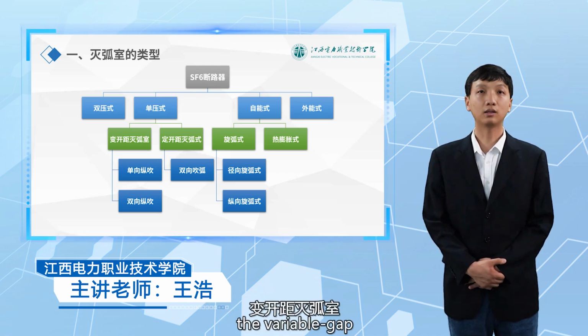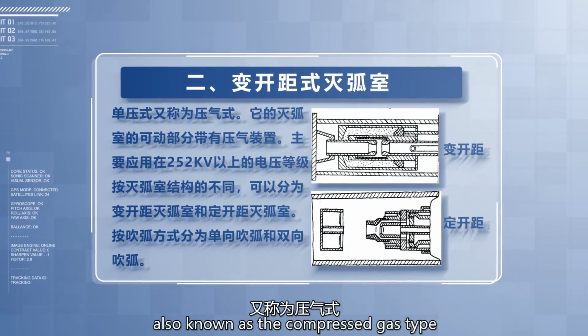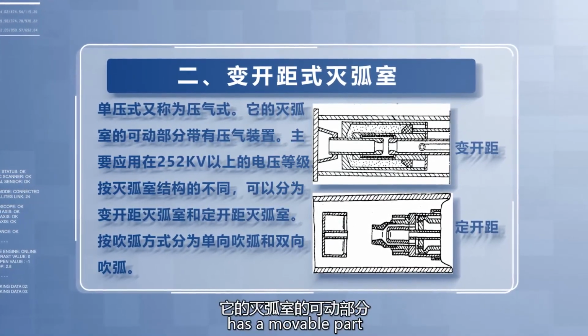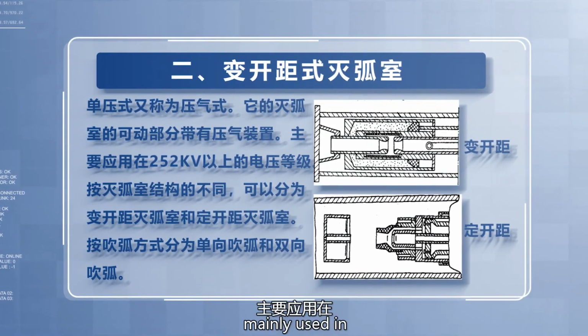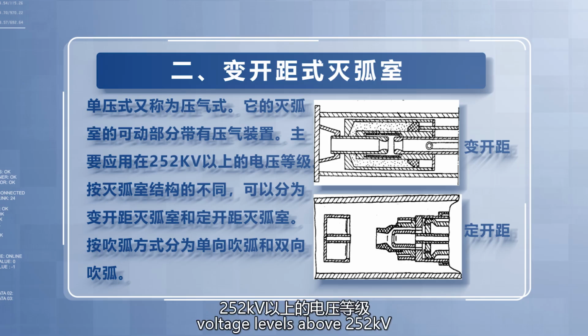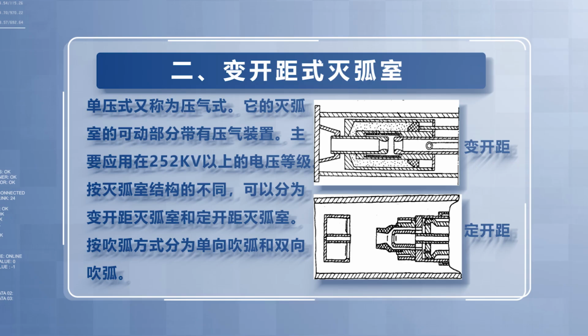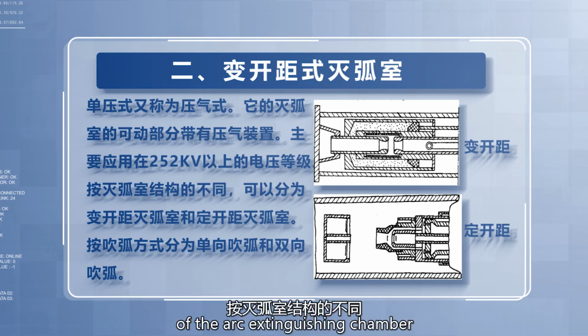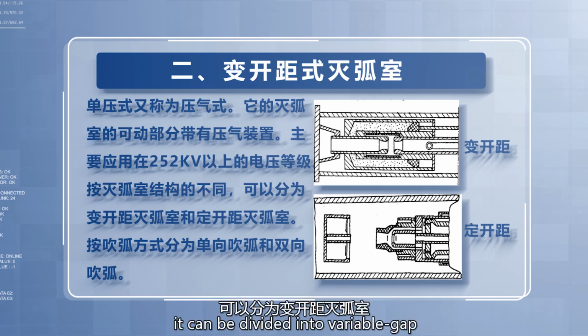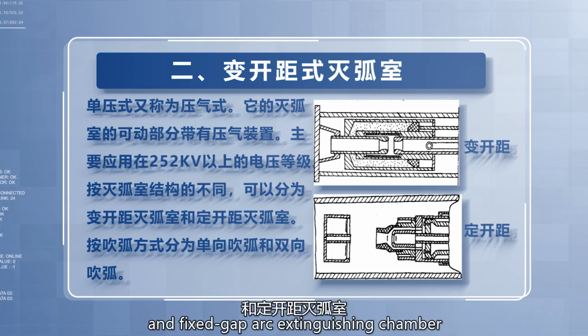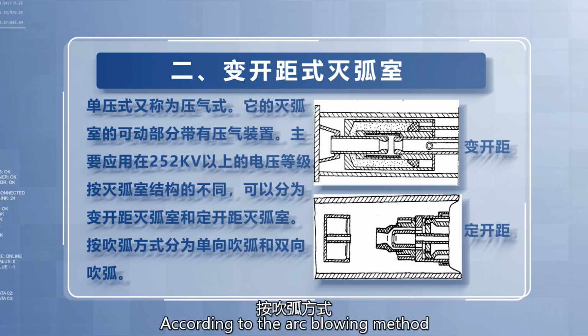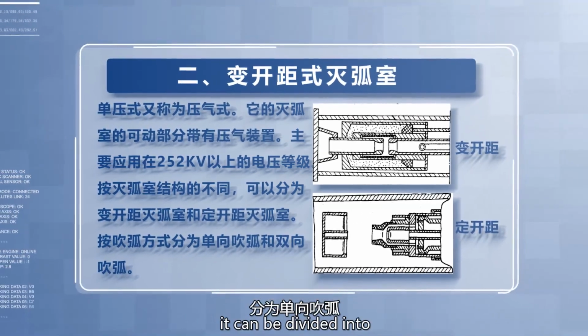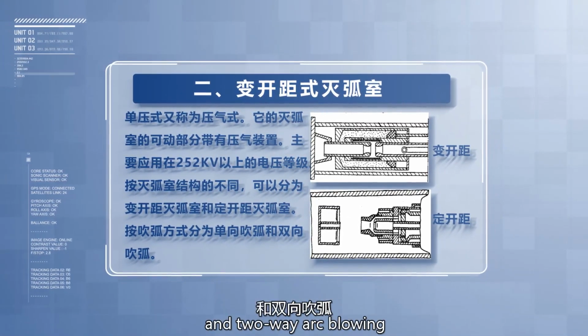Next, we will introduce the variable gap arc extinguishing chamber and the fixed gap arc extinguishing chamber. The single pressure type, also known as the compressed gas type, has a movable part with a compression device, mainly used in voltage levels above 252 kilovolt. According to the different structures of the arc extinguishing chamber, it can be divided into variable gap arc extinguishing chamber and fixed gap arc extinguishing chamber. According to the arc blowing method, it can be divided into one-way arc blowing and two-way arc blowing.